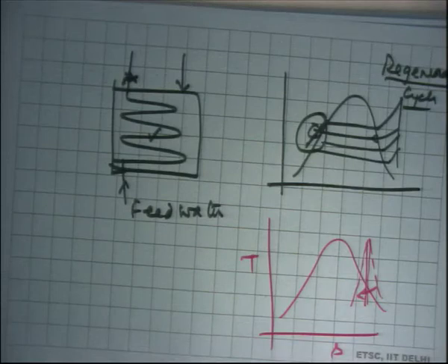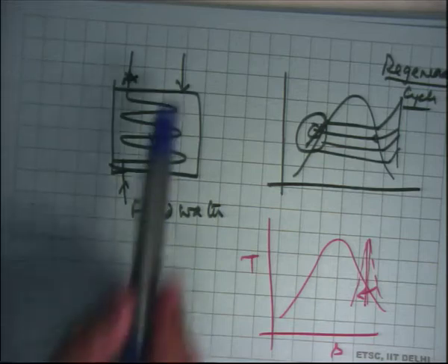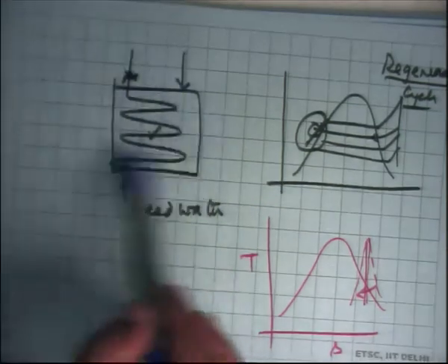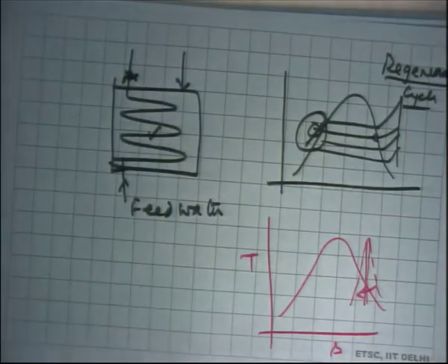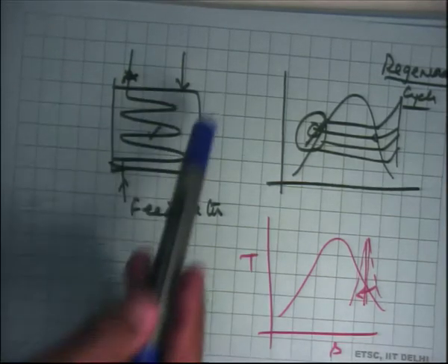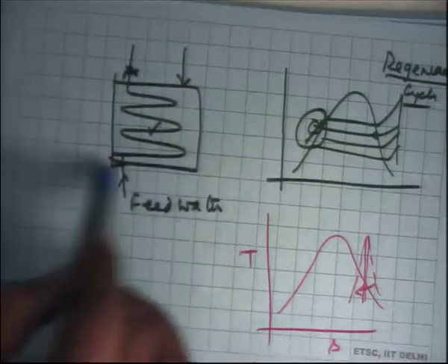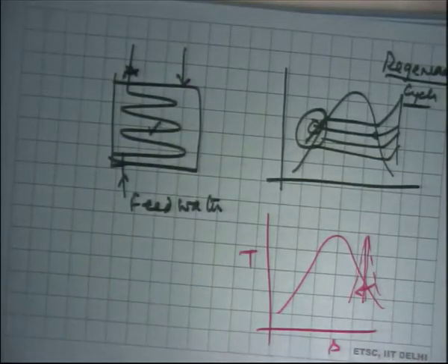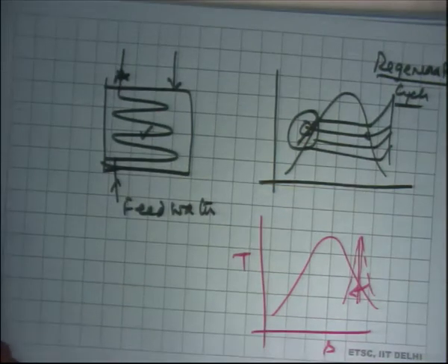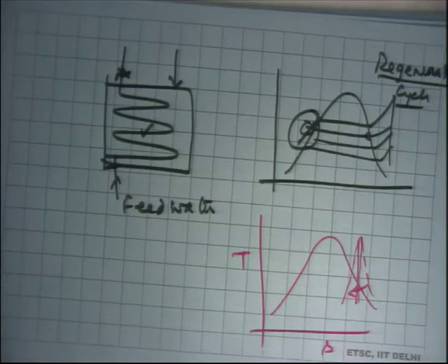Condenser is something that you understand. It again has the steam coming from the turbine like this, and the cooling water that comes from the cooling towers and recirculates back to the cooling towers in pipes like this. The steam condenses and you get what is called a hot well, which is the condensate, which will be at the saturation temperature, and from there you have the condensate extraction pump, which by design should avoid cavitating because the water that is being taken is already at its vapor pressure.